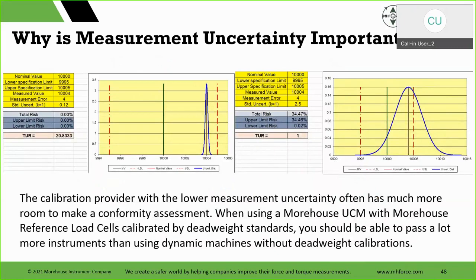Why is measurement uncertainty important? That last graph, we were talking about the accuracy, basically that bias and precision. The calibration provider with a lower measurement uncertainty often has much more room to make a conformity assessment. When using a Morehouse UCM with Morehouse reference cells calibrated by deadweight standards, you should be able to pass a lot more instruments than using dynamic machines without deadweight. And that's what we're comparing here, right? The customer has a 10,000 pound device. We set the limit at plus or minus 5 pounds using one machine.